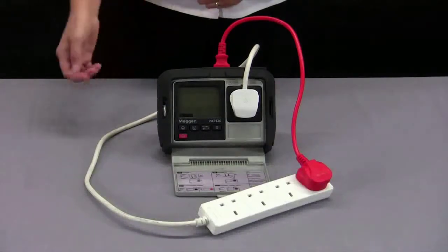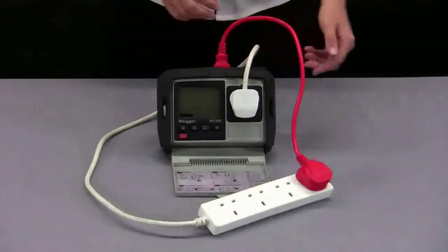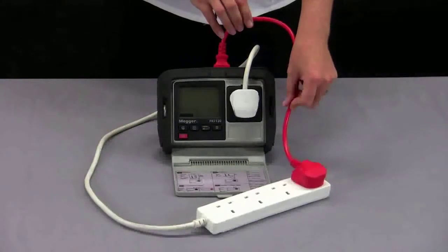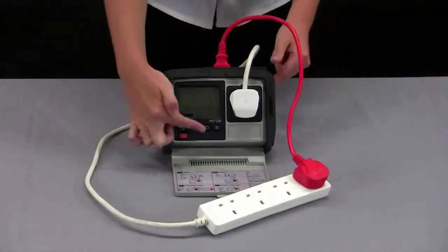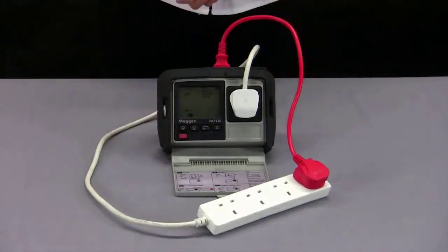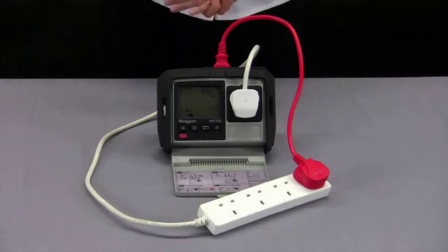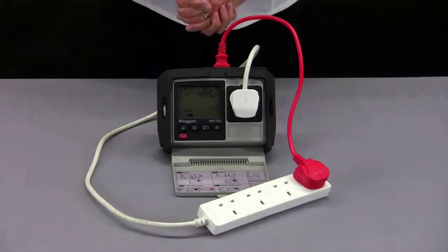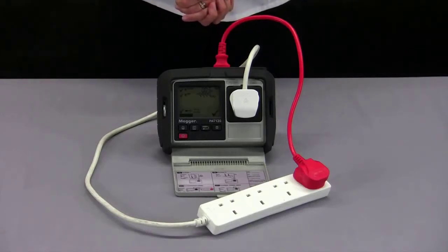For testing extension leads, I have my lead plugged in and linked back using the red IEC extension lead adapter. I can then press my extension lead button and begin the test. My earth continuity test comes first, followed by insulation resistance. I have set to 500 volts, but for surge protected leads you might want to select 250 volts. It will then indicate the polarity is correct and my pass or fail will be indicated on the right hand side.